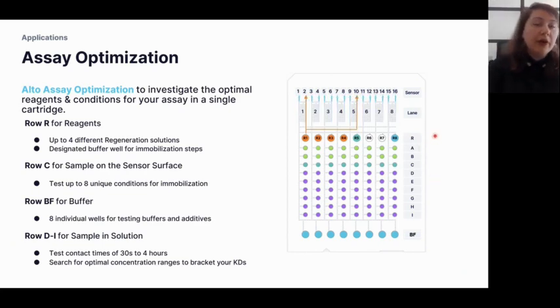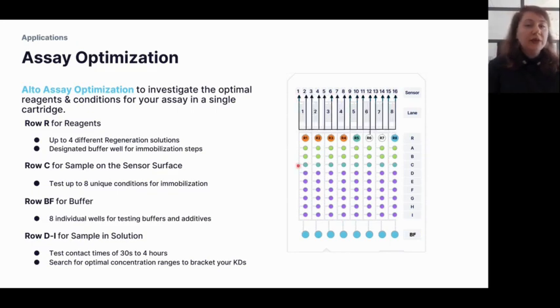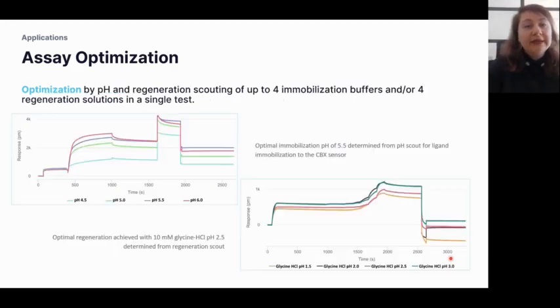In well R8 we have our running buffer for all ligand immobilization steps. In row C, because we have eight wells, we can test up to eight unique conditions for immobilization. The buffer wells — eight in total — can be tested for different buffers or additives like BSA or higher concentrations of Tween. For rows D through I, we can change either the contact time, ranging from 30 seconds up to four hours, or test different analyte concentrations to better bracket our KD.